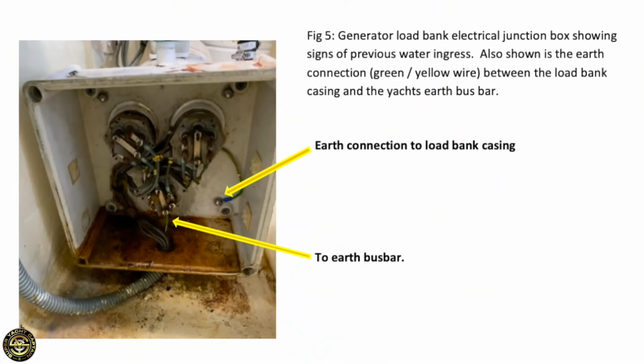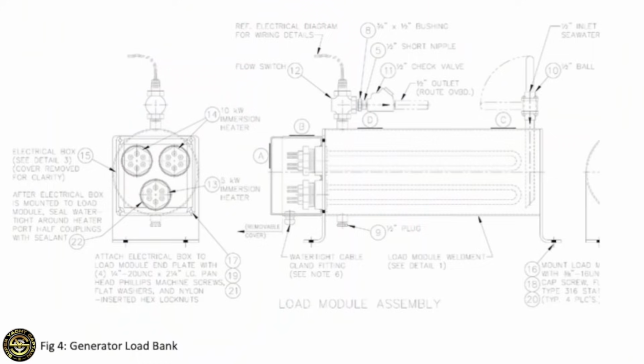The investigators found evidence of water ingress where the electrical cables were inside the canister. It says that it is probable that the lack of effective earth bonding for the load bank casing resulted in the engineer suffering electrocution, by providing a current path between the heating elements and the true earth through his body. This path would have been completed via an earthed component in the vicinity of the load bank. So the electricity is coming through into the giant kettle. The electrical cables on the heating element have lost their insulation.